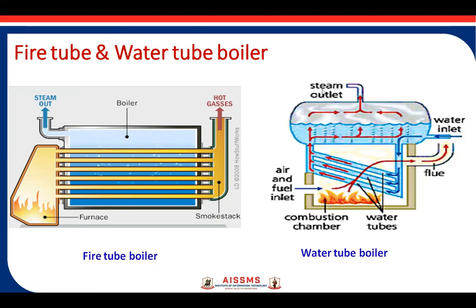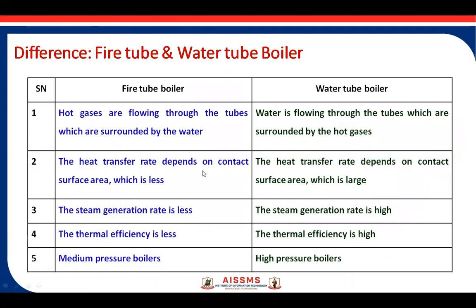We can see the difference between water tube and fire tube boilers. In a fire tube boiler, hot flue gases flow through the tubes which are surrounded by water. In a water tube boiler, water flows through the tubes which are surrounded by hot gases. The heat transfer rate depends on contact surface area, which is less in fire tube boilers and greater in water tube boilers — that is why water tube boilers are used for industrial purposes.